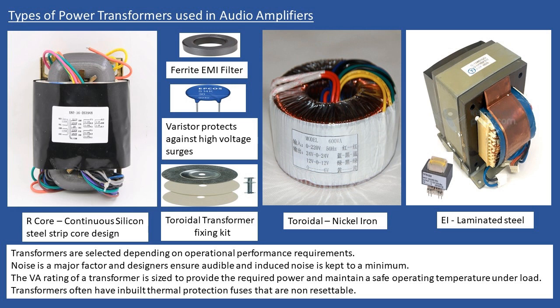And then you will find many of these power transformers have an inbuilt thermal protection fuse, and if the transformer overheats, that thermal protection fuse could operate, and it would just go open circuit. It's non-resettable, it doesn't reset once the transformer temperature lowers, and that would render the transformer open circuit, and then you would have to replace it. But we'll come back to that a little bit later.